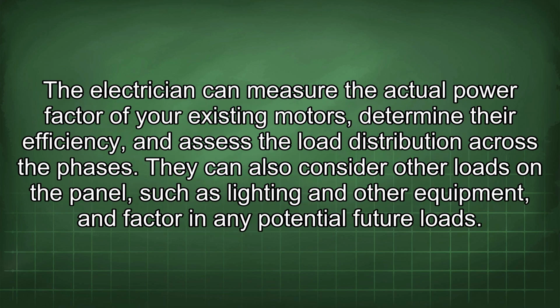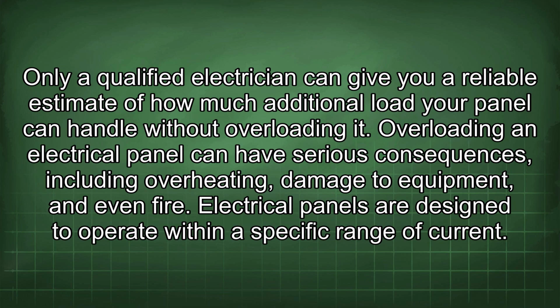The electrician can measure the actual power factor of your existing motors, determine their efficiency, and assess the load distribution across the phases. They can also consider other loads on the panel, such as lighting and other equipment, and factor in any potential future loads. Only a qualified electrician can give you a reliable estimate of how much additional load your panel can handle without overloading it. Overloading an electrical panel can have serious consequences, including overheating, damage to equipment, and even fire.